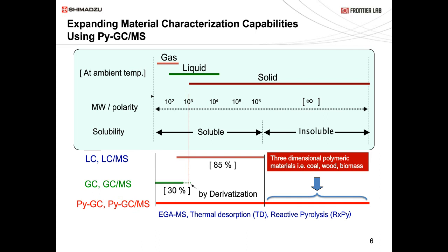Now let's discuss how you can extend material characterization using pyrolysis GCMS. At room temperature, a substance can be gas, liquid, or solid depending on molecular weight. Some solid samples are soluble in solvent, so you could use analytical techniques such as LC, LCMS, GC, or GCMS. However, there is a range of solid samples that are insoluble in any solvent. That's where PyGC or PyGCMS comes in and expands the capabilities of your GCMS—not only can you analyze gas and liquid, but you are also expanding the range of solid samples you can analyze. There is no need for solvent extraction or sample pretreatment before the analysis; you could just inject a solid sample as it is into the furnace.